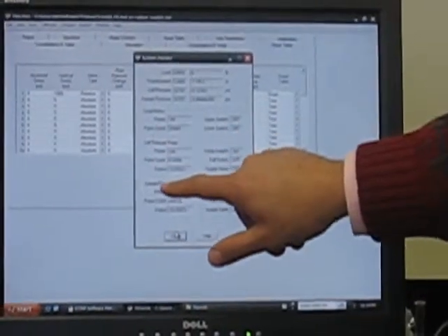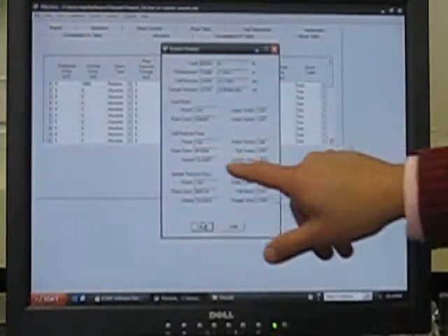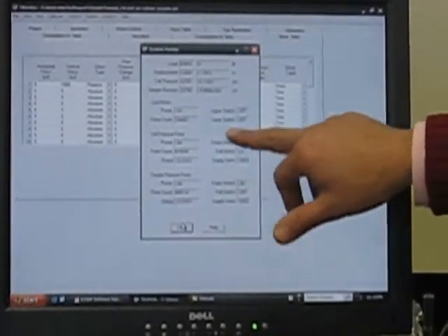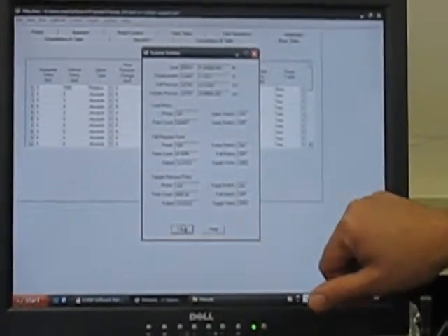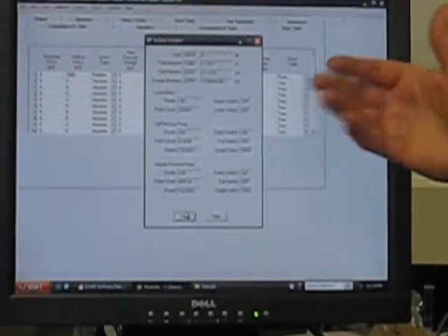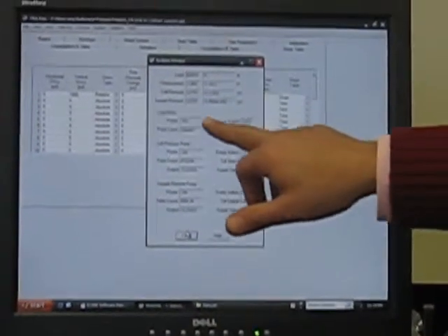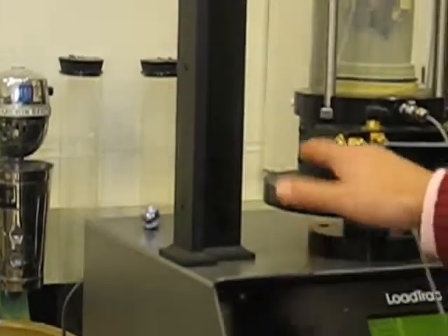And then the motors for the load frame, cell pressure, and sample pressure are on. And limit switches - don't worry about limit switches for the flow pump because the software automatically empties the flow pump and fills it to the desired capacity that you specify in the software. The load frame - you do need to have the platen at a certain position away from the lower limit switch.